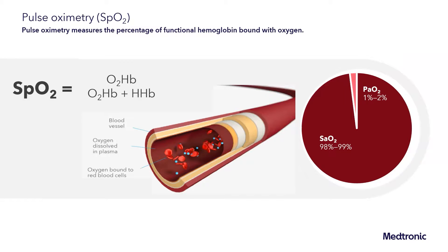Pulse oximetry measures the percentage of functional hemoglobin bound with oxygen. Ninety-eight to ninety-nine percent of oxygen is bound to hemoglobin as measured by the SaO2, whereas only one to two percent of oxygen is circulating in the plasma as measured by the partial pressure of arterial oxygen. The SpO2 is calculated by dividing oxygenated hemoglobin by the sum of oxygenated and deoxygenated hemoglobin.